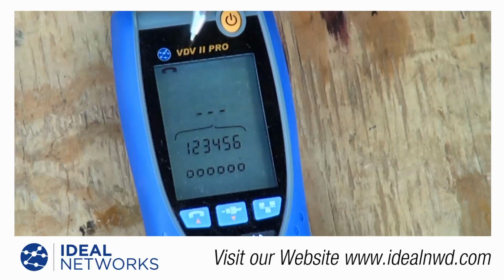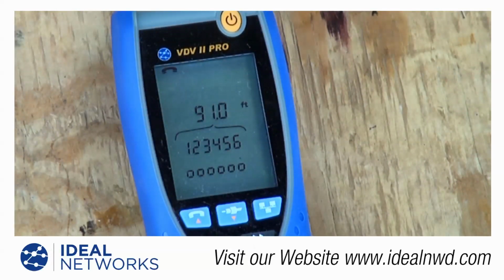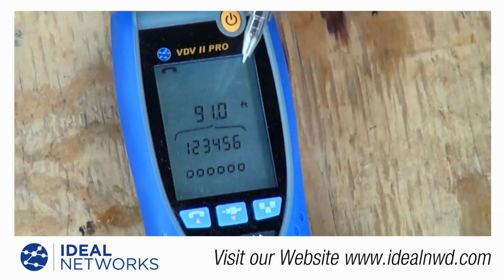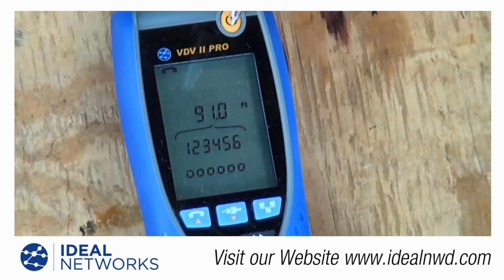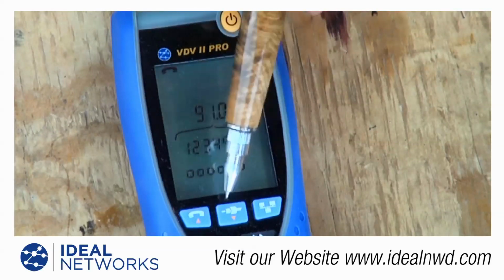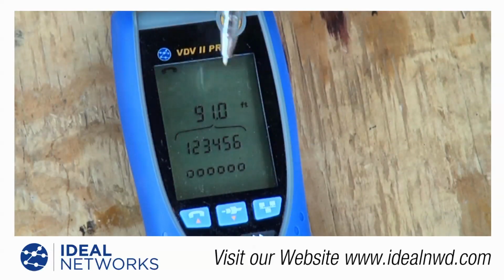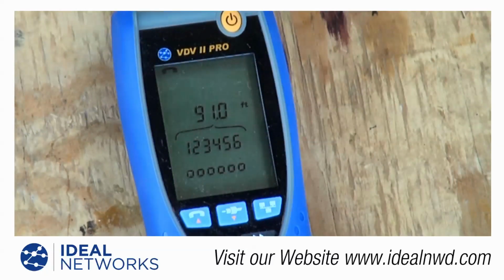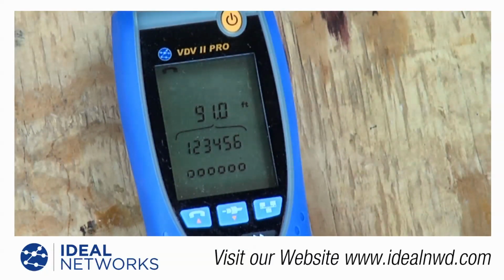If I push the phone button, it's showing about 90 feet long, but we're seeing about 100 here. That's because the tester allows you to set the NVP for each different type of cable and it stores that. Anytime I do phone testing, it's set at about 60-something, coax was set at about 58, and I had the data set at about 72. One nice feature of the VDV is it will store the particular NVP you set, and most coax like RG6 will have about the same NVP, so you'd like to be able to set that.